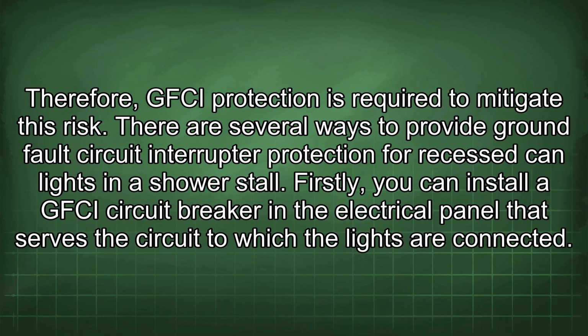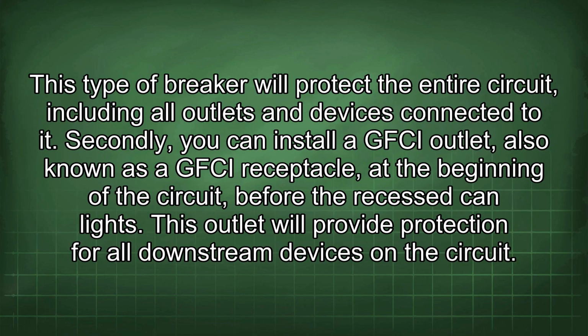There are several ways to provide ground fault circuit interrupter protection for recessed lights in a shower stall. Firstly, you can install a GFCI circuit breaker in the electrical panel that serves the circuit to which the lights are connected. This type of breaker will protect the entire circuit, including all outlets and devices connected to it. Secondly, you can install a GFCI outlet, also known as a GFCI receptacle, at the beginning of the circuit before the recessed lights. This outlet will provide protection for all downstream devices on the circuit.